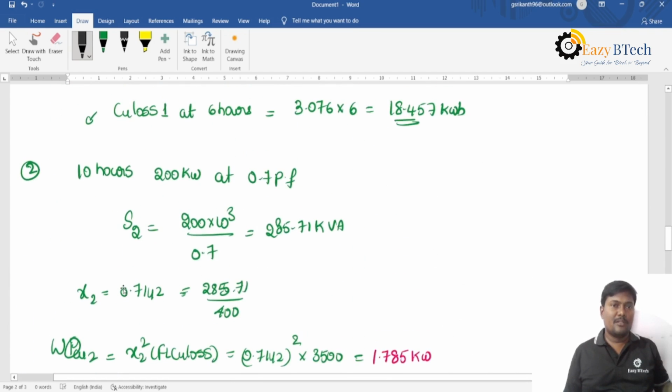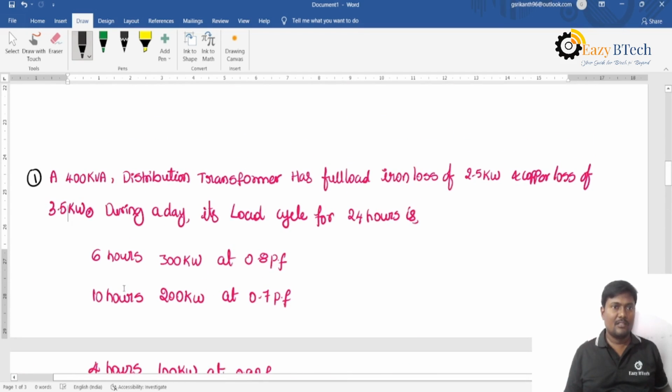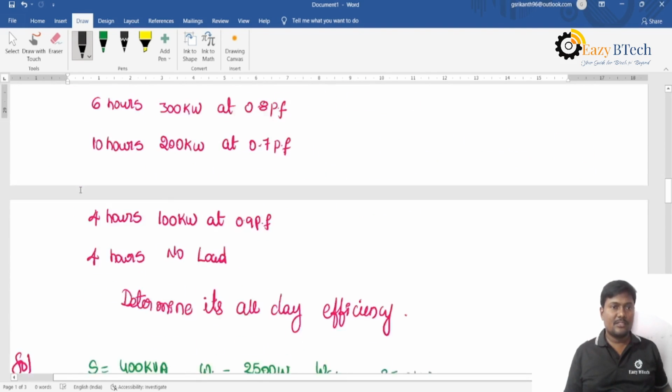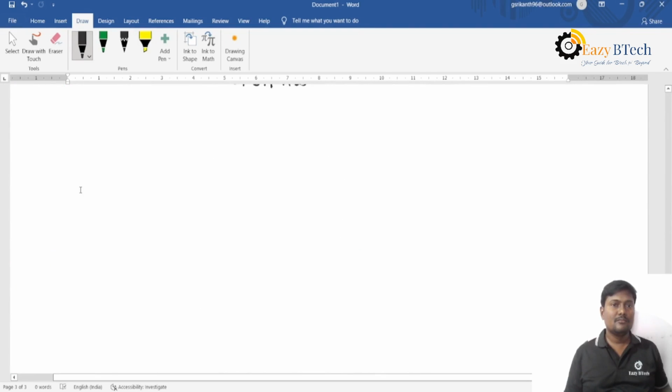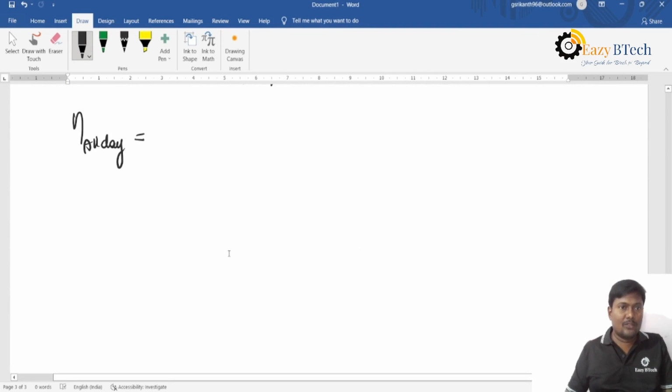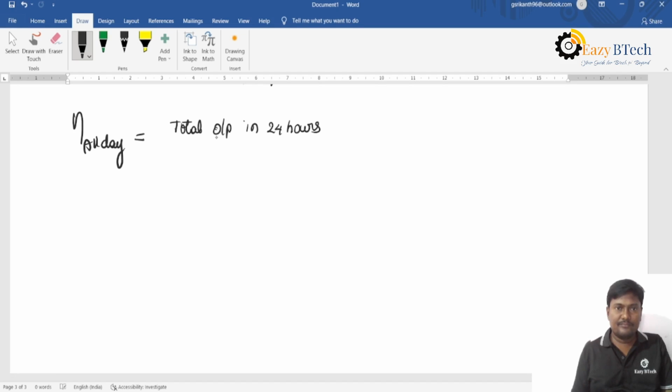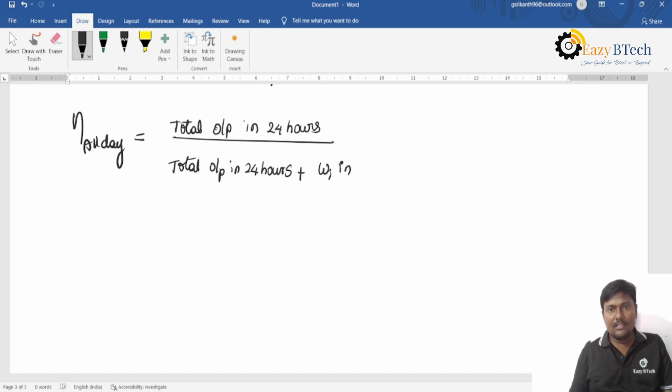Yes, the output power is given in 24 hours, right? So all day efficiency is total output in 24 hours divided by total output in 24 hours plus iron losses in 24 hours plus copper losses in kilowatt hour.